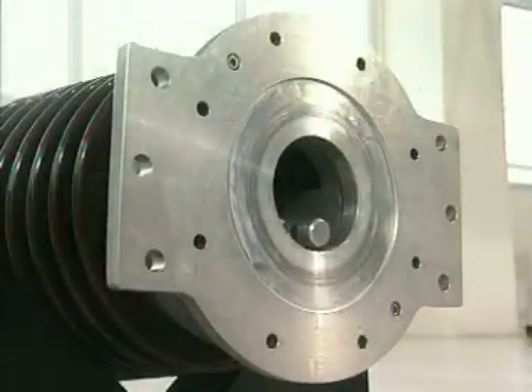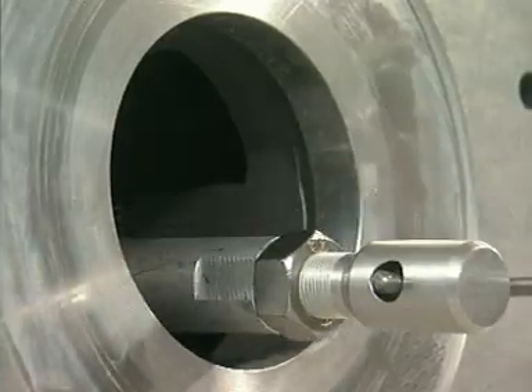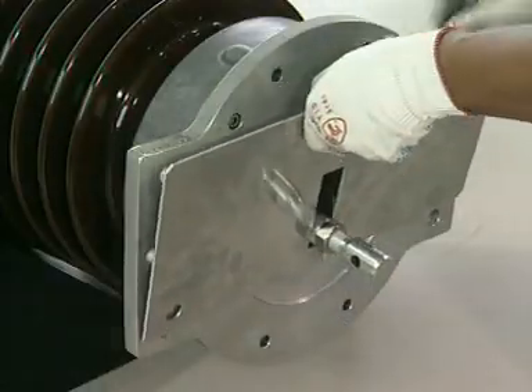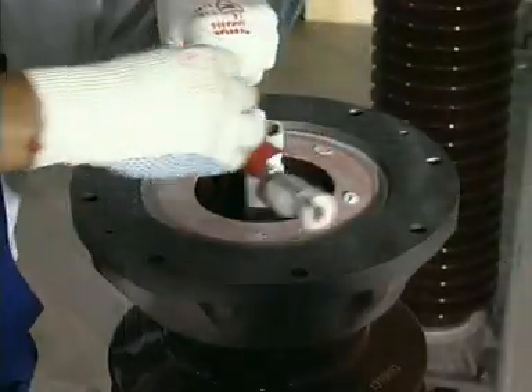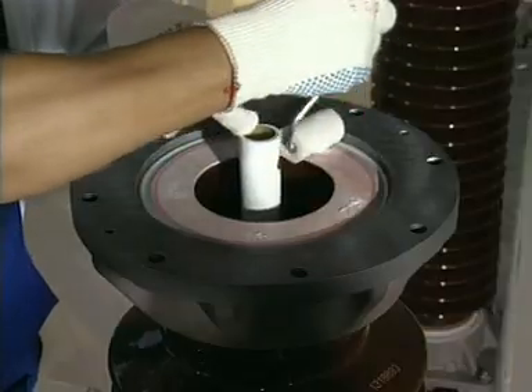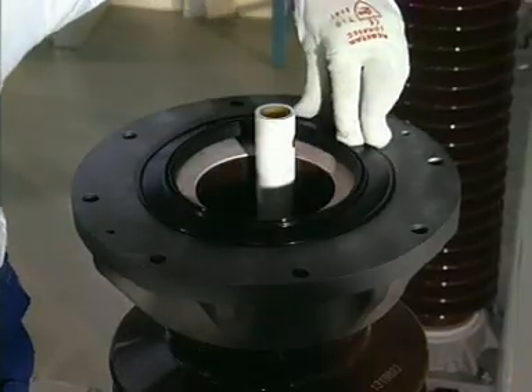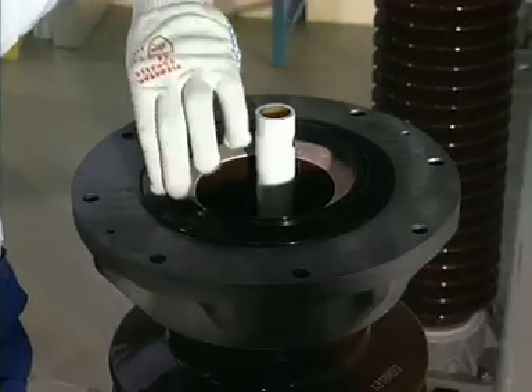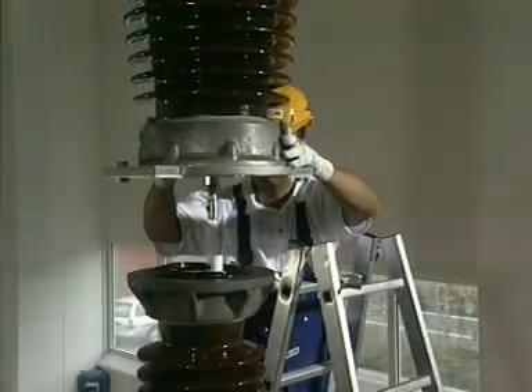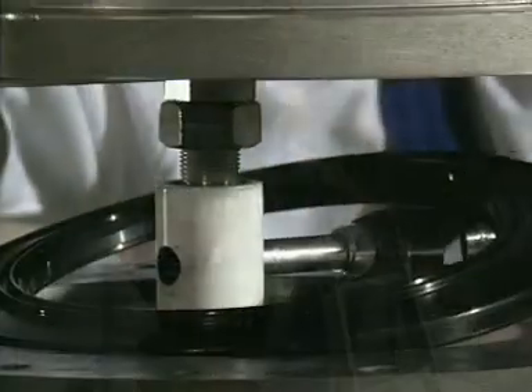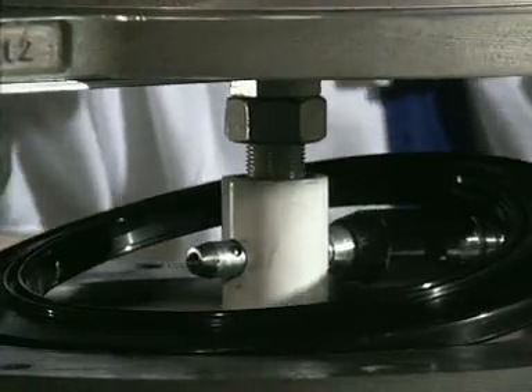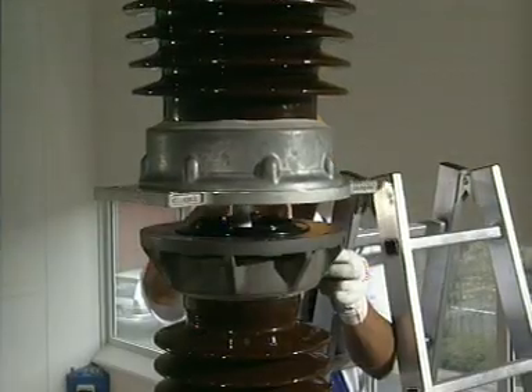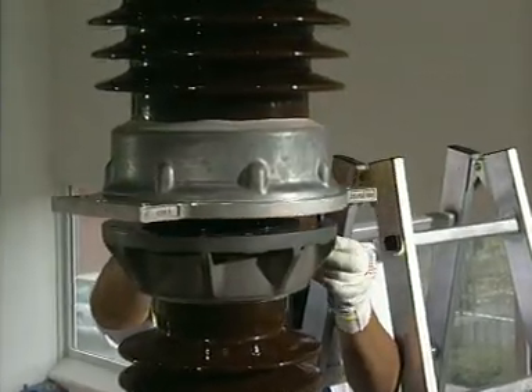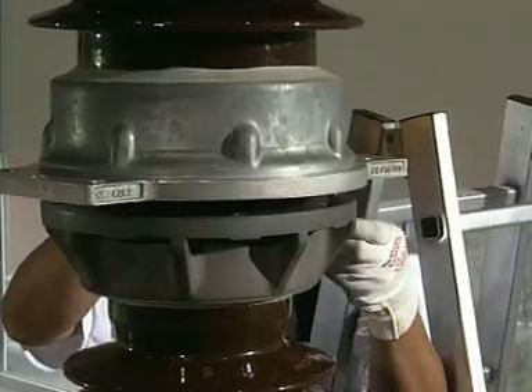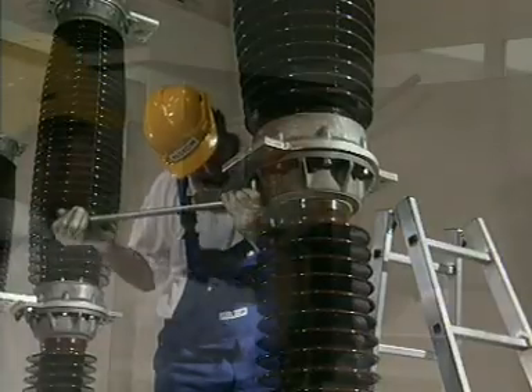Bring the new or conditioned interrupter chamber into the open position and attach the coupling fixture. Grease the sealing surface on the support porcelain and install a new gasket. Lift the interrupter chamber above the support porcelain. Insert the coupling pin and remove the coupling fixture again. Lower the interrupter chamber slowly, insert the bolts and tighten using a torque wrench.